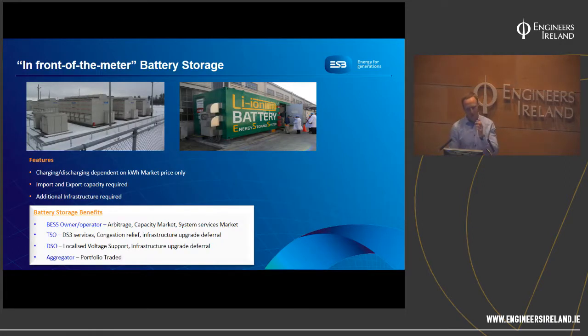Next, in front of the meter storage. Traditionally it would have tended to be larger in capacity, but there are large scale behind the meter storage options these days, so you can't really make that distinction. So in front of the meter storage is essentially any storage that is not co-located directly with a load or co-located directly with generation—it's purely depending on a grid connection. As such, the charging and discharging of the battery is purely dependent on the kilowatt hour market price and the availability of the battery.